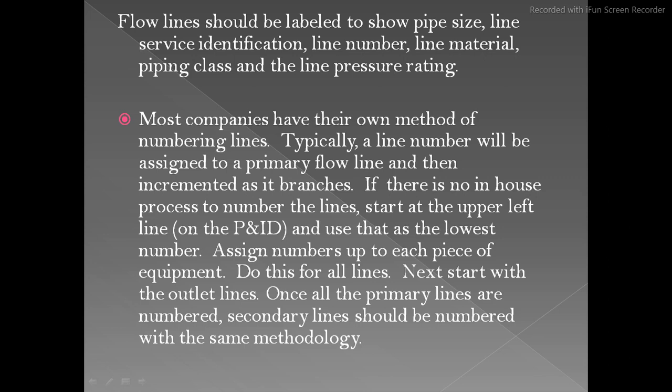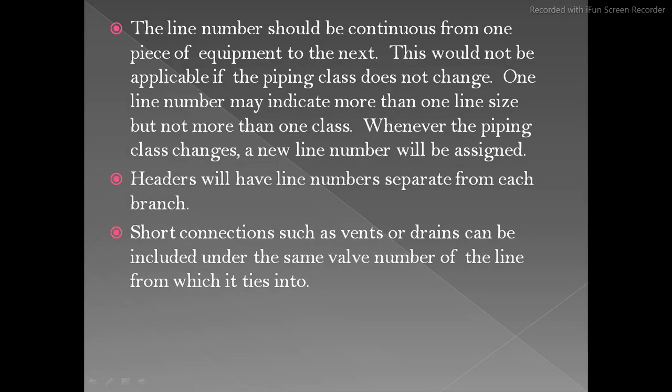Next, start with the outlet lines — meaning when they start with the equipment outlet. If you have a tank or a pump, whatever the outlet lines are, they start numbering there. Once all primary lines are numbered, secondary lines should be numbered with the same methodology. The line number should be continuous from one piece of equipment to the next.